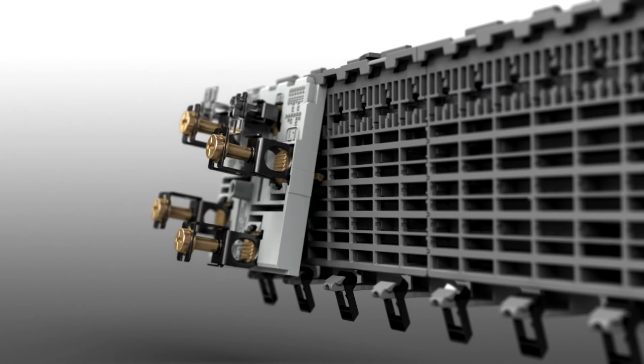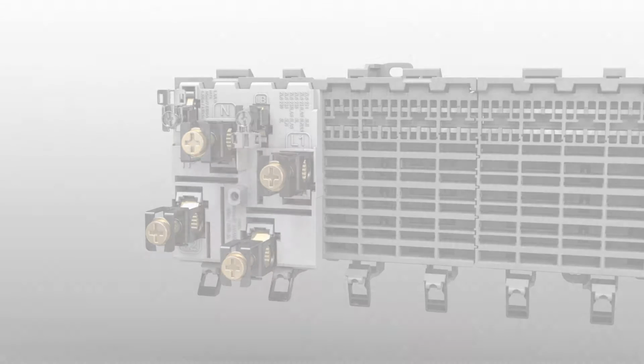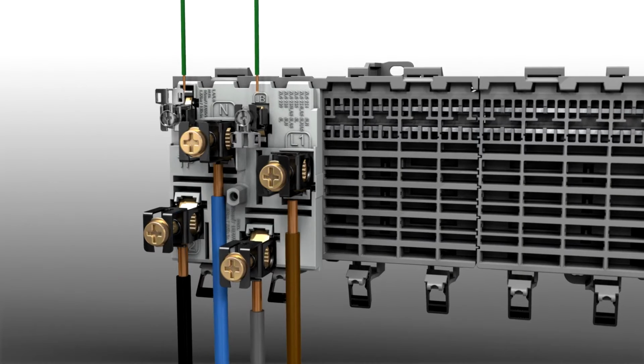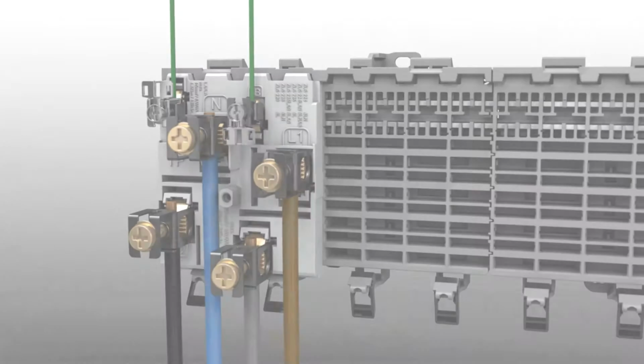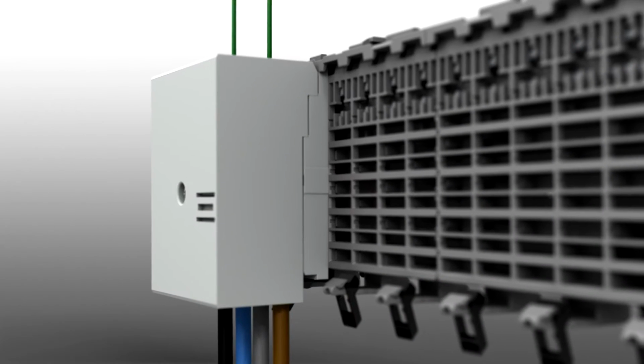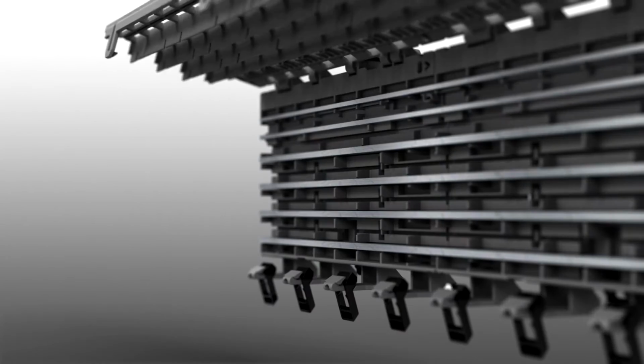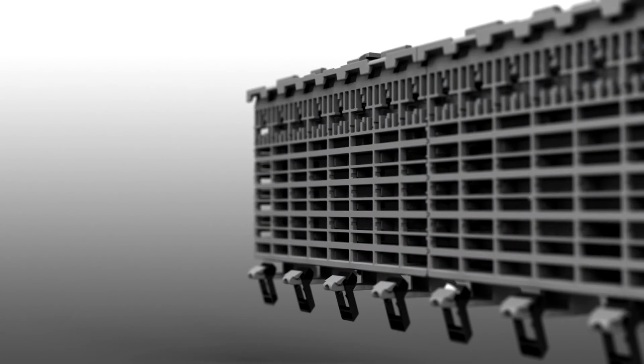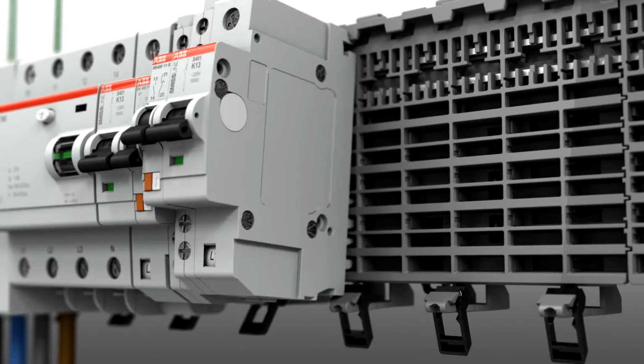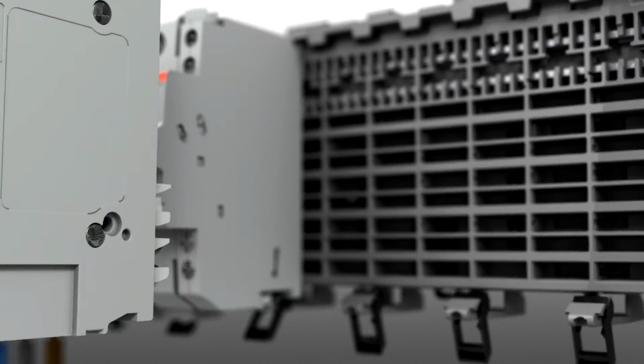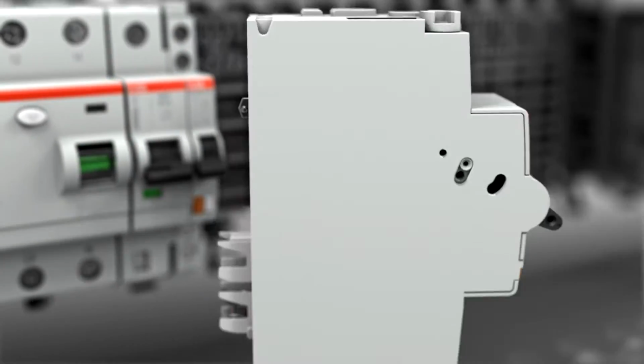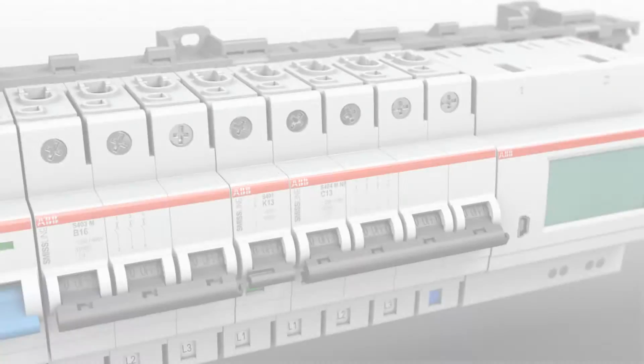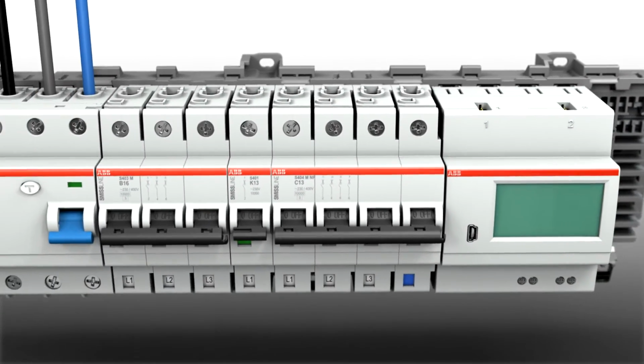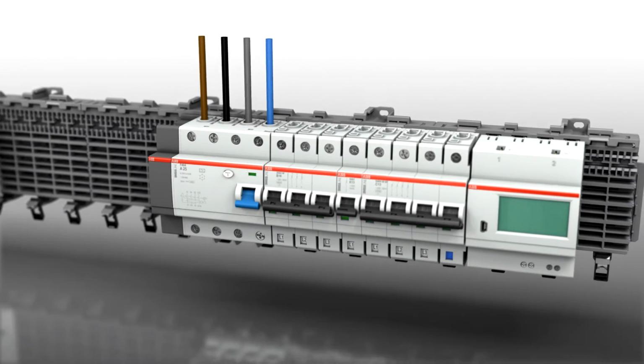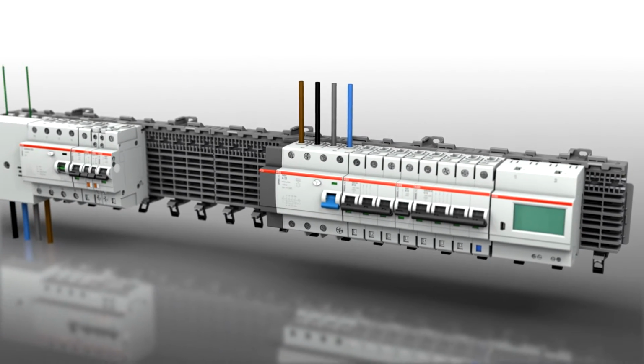The power can be supplied to the bus bar system via an incoming terminal block or directly via a protection device. The bus bar system is closed in a way that ensures full protection against direct contact. This enables load-free plugging in and unplugging of live devices without the need for personal safety equipment. SMISSLINE TP is specially developed for use in the critical power market, wherever a high level of availability is required.